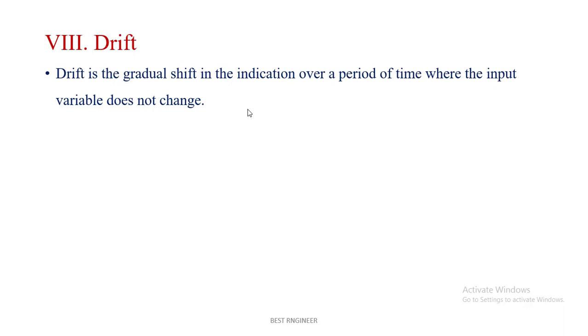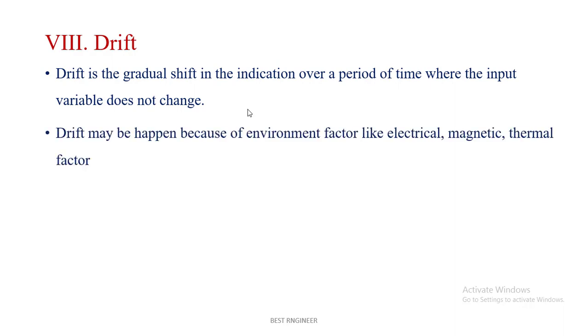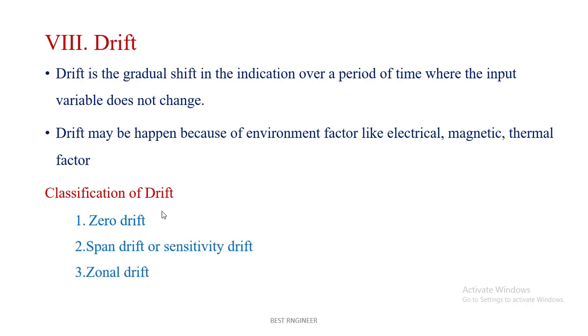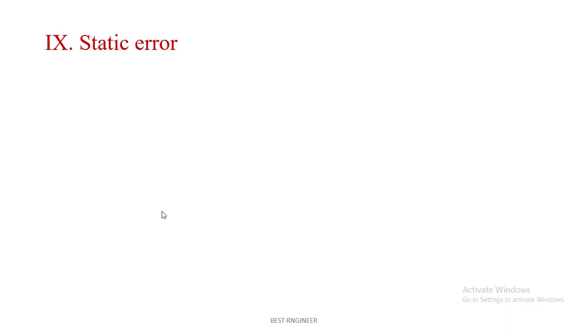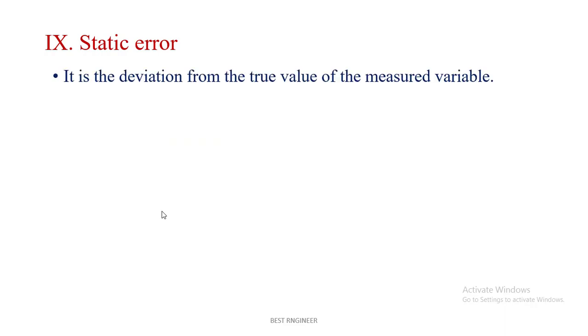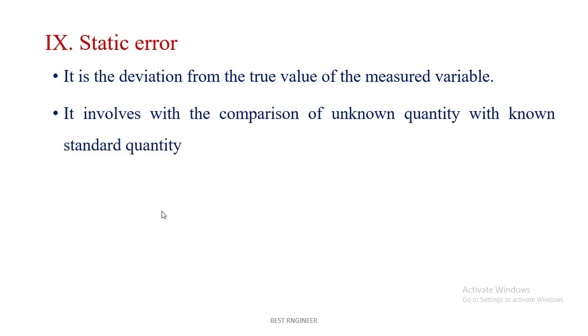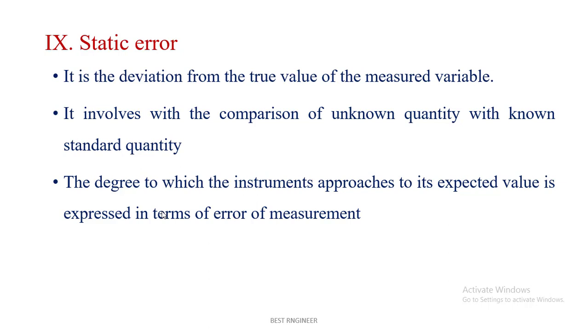Drift is the gradual shift in the indication over a period of time where the input variable does not change. Drift may occur due to environmental factors like electrical, magnetic, and thermal factors. Drift is further classified into three types: zero drift, span drift or sensitivity drift, and zonal drift. Static error is a deviation from the true value of the measured variable. It involves comparison of an unknown quantity with a known standard quantity, and the degree to which an instrument approaches its expected value is expressed in terms of the error of measurement.